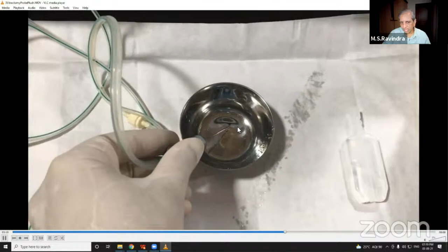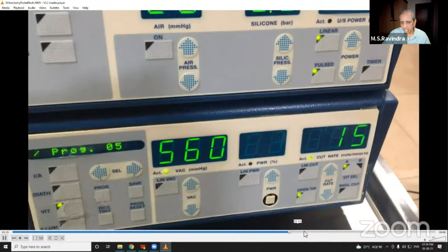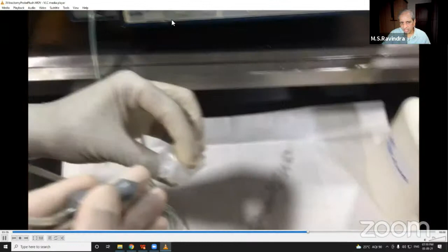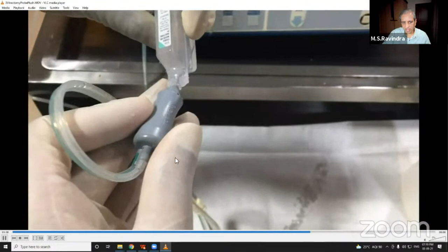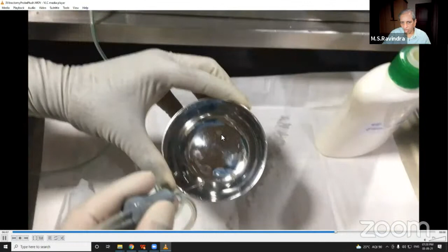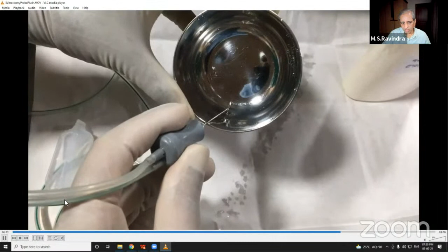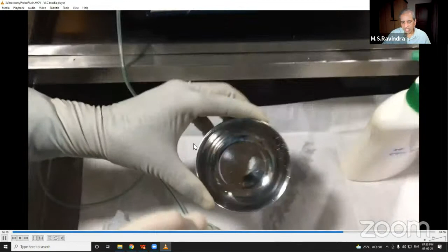So I'm sucking water into it, and it's supposed to clean the inside portion. After that, I suck air in it. At the end of it, I suck air. Then I aspirate the distilled water from a 15 ml distilled water bottle, and then I take alcohol in it and aspirate. The alcohol, 80% or even 100% is fine. It's going to remove all the water bubbles from inside, and then I aspirate only the air in it, and then it becomes really pristine, really gets cleaned. Then it goes into the autoclave.